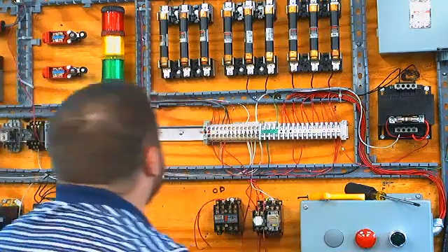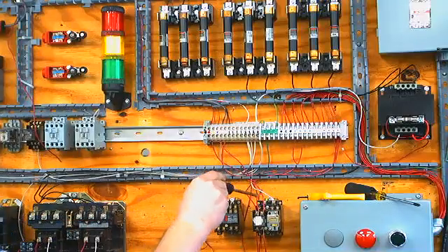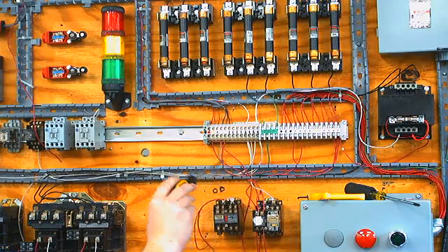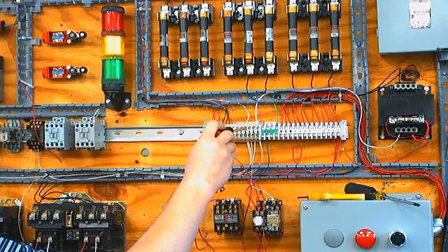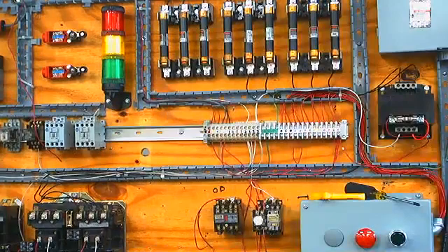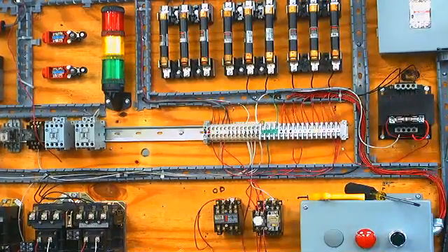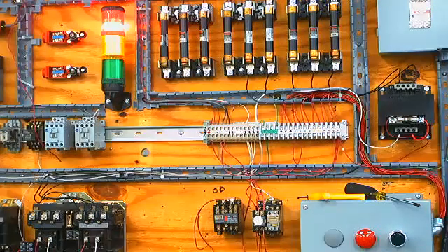Right, and I am done because the coil's neutral has already been made up, and the neutral for the lights, which is shared between the three of them, has already landed here. So I can turn this thing on and see what it does. But what did we say this thing was going to do when I push the button? Well, when I turn the disconnect on, yes, the red light will come on. See? Red light's on. When I push the button, 3 seconds, green light.